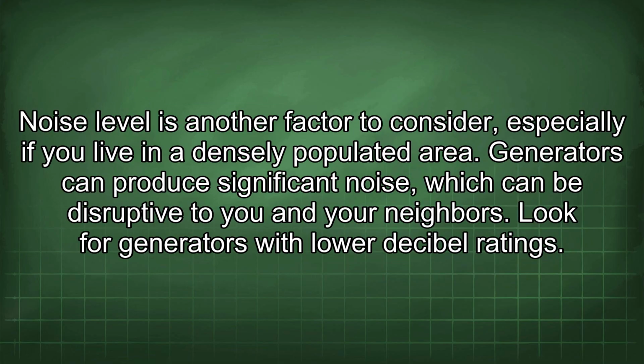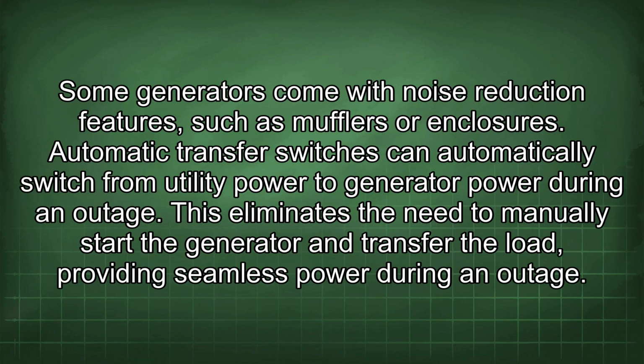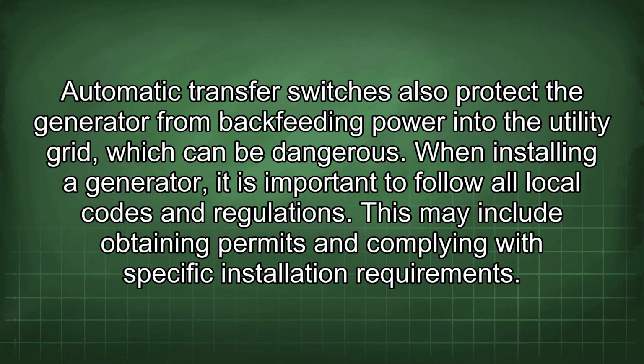Noise level is another factor to consider, especially if you live in a densely populated area. Generators can produce significant noise which can be disruptive to you and your neighbors. Look for generators with lower decibel ratings. Some generators come with noise reduction features such as mufflers or enclosures. Automatic transfer switches can automatically switch from utility power to generator power during an outage. This eliminates the need to manually start the generator and transfer the load, providing seamless power during an outage. Automatic transfer switches also protect the generator from backfeeding power into the utility grid, which can be dangerous.